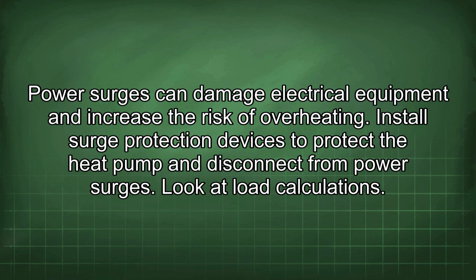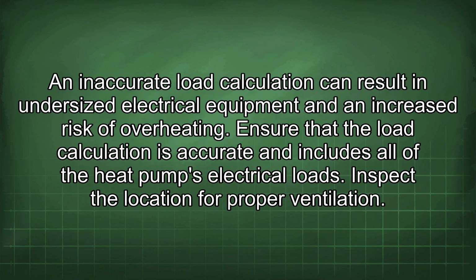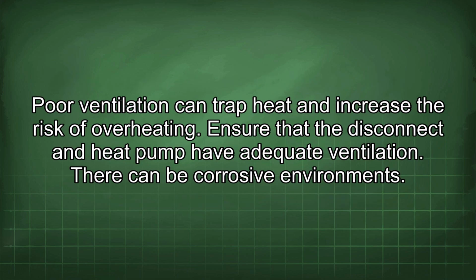Look at load calculations. An inaccurate load calculation can result in undersized electrical equipment and an increased risk of overheating. Ensure that the load calculation is accurate and includes all of the heat pump's electrical load. Inspect the location for proper ventilation. Poor ventilation can trap heat and increase the risk of overheating. Ensure that the disconnect and heat pump have adequate ventilation.